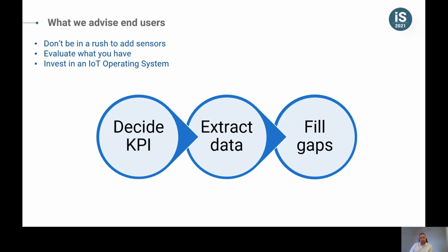Once you decide your KPIs, go extract the data you have, because in reality you already have most of that data available. If you want to know how often people use the bathrooms, don't rush to put in a sensor—you probably already have an automatic lighting system there. Extract the motion data from the lighting system instead of adding another sensor. Once you have all the data you can get, fill in the gaps: if there's something your current data can't tell you, go add new sensors to fill that gap.